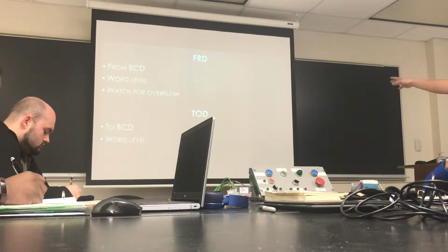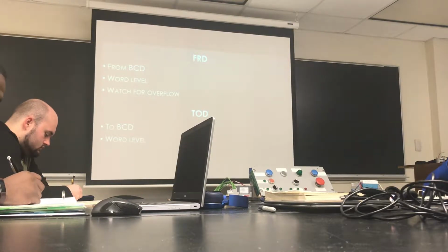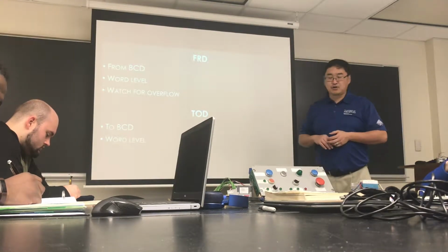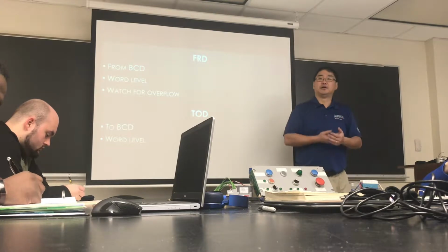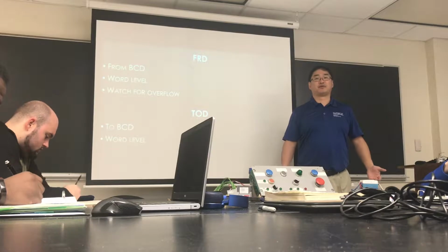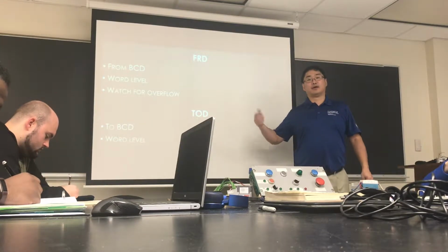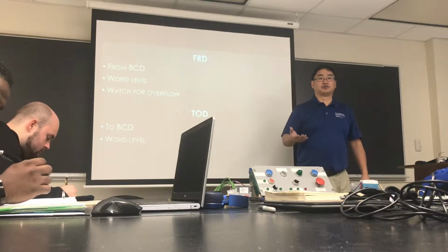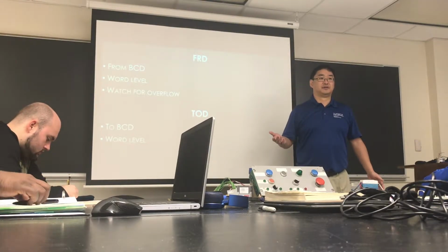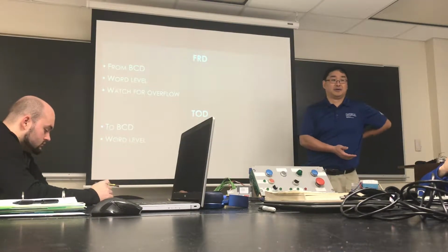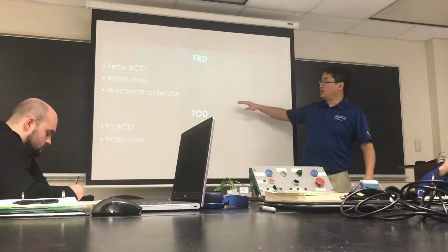I shot myself in the foot. My little conveyor downstairs, I swapped out the PLCs on it, I put a MicroLogix on it, and rewrote the program for it, and like an idiot totally forgot about that, and it kept crashing after about 40 minutes. I couldn't figure out why until I realized, oh, math overflow, because I was trying to count and do some movements and everything else into a standard integer which stops at 32,000 and change. And I was trying to dump a count of 1,000,000 into it. It didn't like it. And you'll get that overflow.